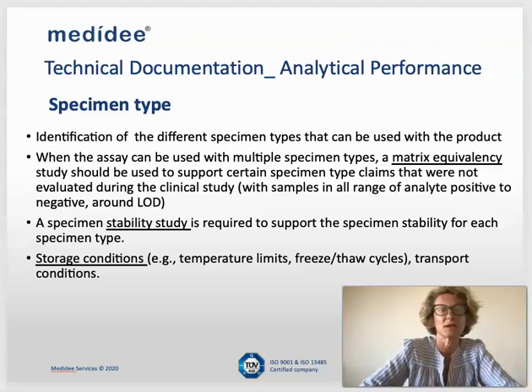Also, the analytical performance of the device really depends on the repeatability and reproducibility of the result. It means that we have to make sure that when using our device, every time we will obtain the same measurement. So we have the repeatability, which is to show that within the same run, we will obtain the same results, the same measurement. Also, that independently of the day of the run, the operator using the device, or the instrument which is used, we will obtain the same measurement of the analyte.